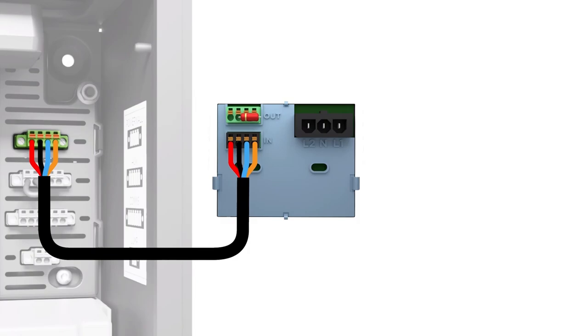For single Powerwall 2 installations, plug the green communication connector with resistor into the top left corner labeled OUT inside the wiring compartment. Make sure the connectors are fully seated since there is no locking mechanism.